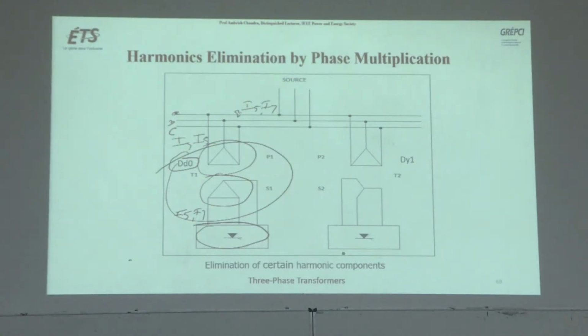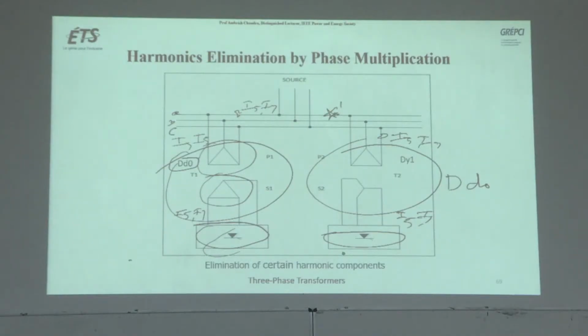Now you have a similar transformer here, DD0, and these loads are identical. It is generating I5 and I7, which is transported here, I5, I7, which will go here this way. Now you have 2 I5 and you have 2 I7. See? So this is what is happening. All the harmonics are adding up, because the engineer said, okay, the first line is working fine and the second line should also work fine.